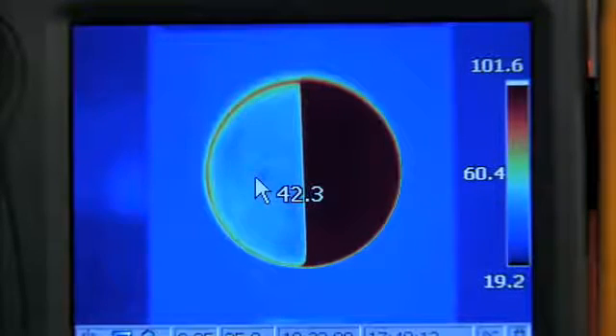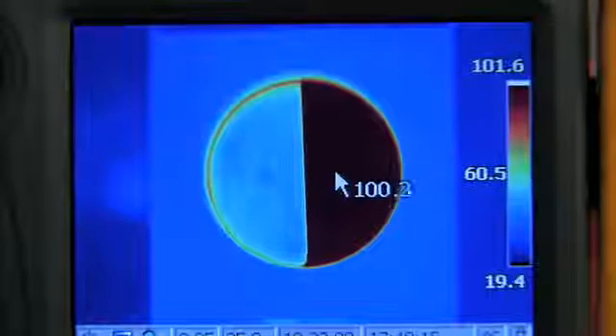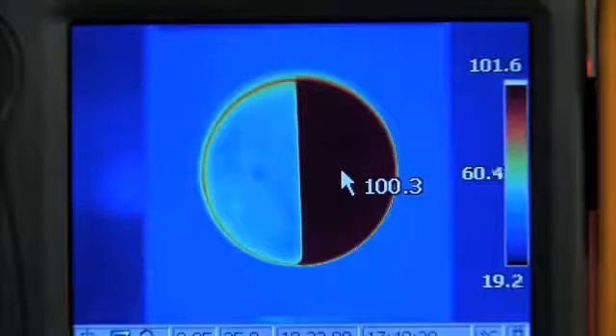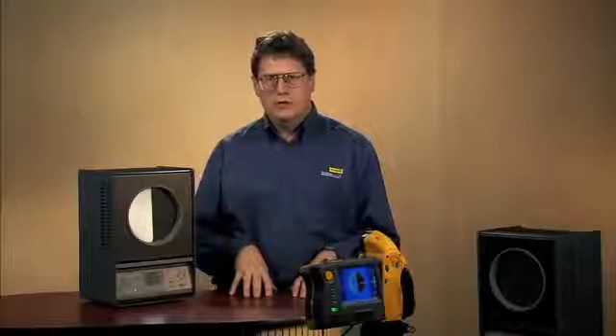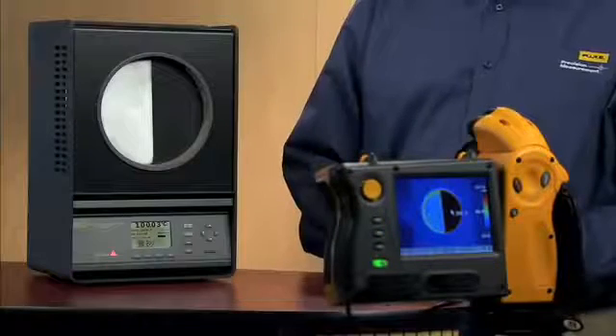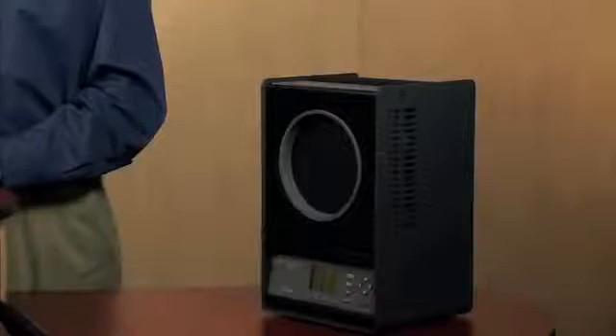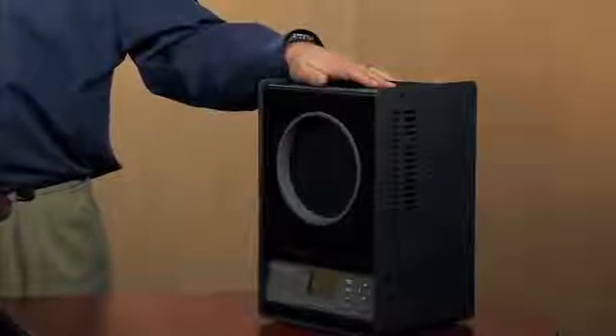What it means is that we need to know the emissivity and be able to match the surface's emissivity with our IR thermometer. This is kind of hard to do, though, because surfaces generally don't have a fixed emissivity. The solution is to do a radiometric calibration on your surface. This is what we do with the Fluke Precision Infrared Calibrator.